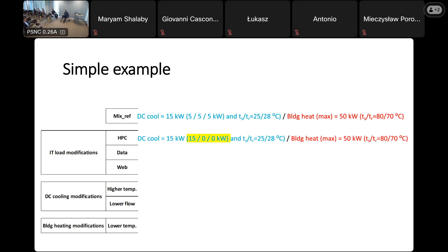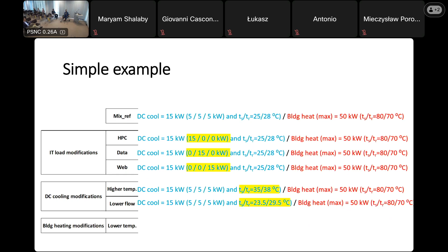What was the difference between this reference case and the other cases? When we look at the modification of the IT load, we just move all IT load to one type: HPC, data, or only web. So the whole 15 was allocated to only one type of task, but the other things are the same. Next, in the data center cooling modification, we change the temperature and flow through the cooling system. Here the temperatures are raised, but the difference is the same. And here the mean value is the same as in the reference case, but the difference is higher, which means the flow is lower. If we have to deliver the same cooling power and we increase the difference, the flow of this cooling liquid will be lower.